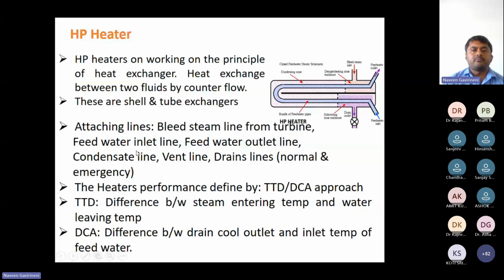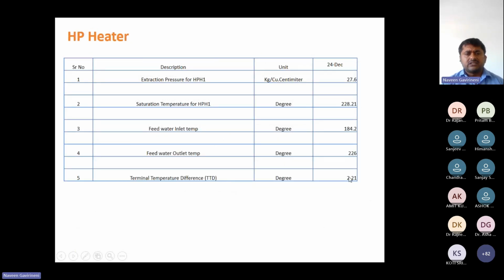So with the bleed arrangement, bleed steam comes from the turbine to heat up the feed water or condensate water. So this is the result. We are getting the TTD, which should be less than 4. If the TTD is more than 4 degrees, what happens? Initially we could say that fouling has happened in the tubes of the heater.